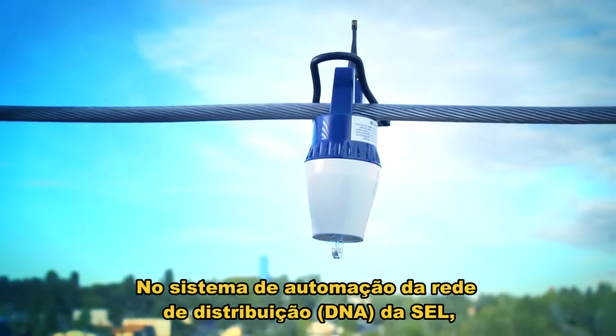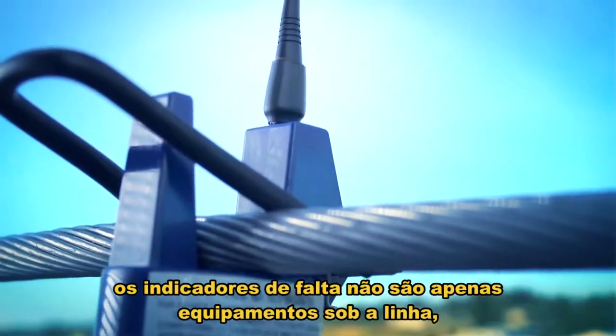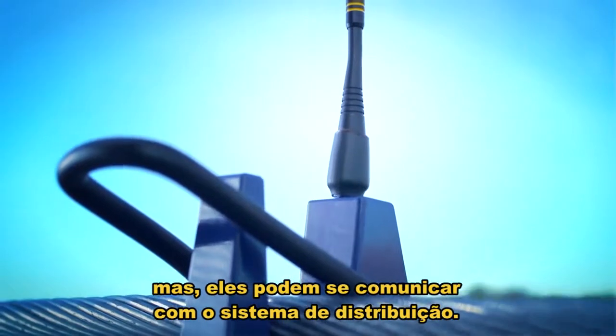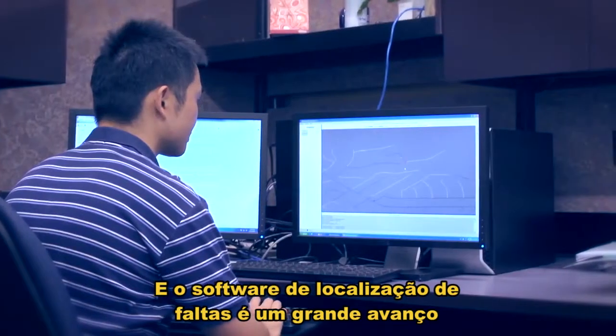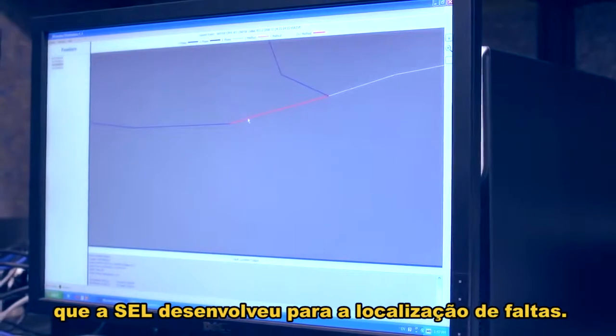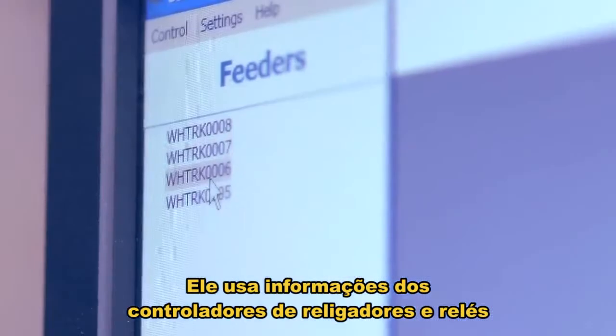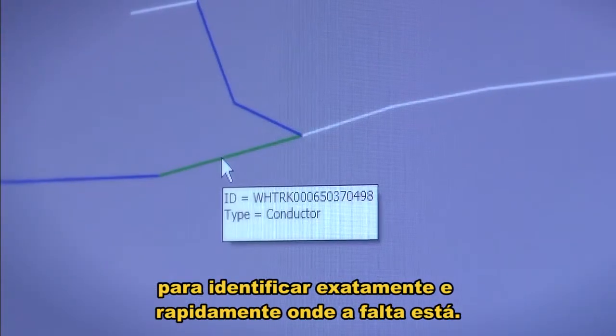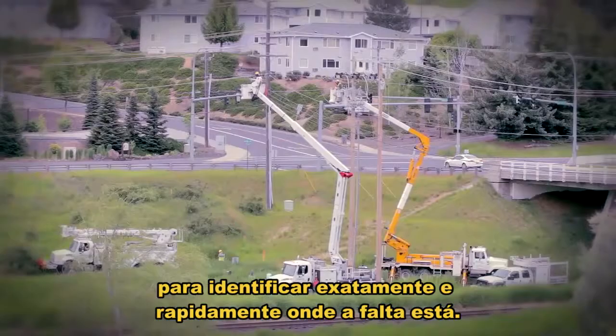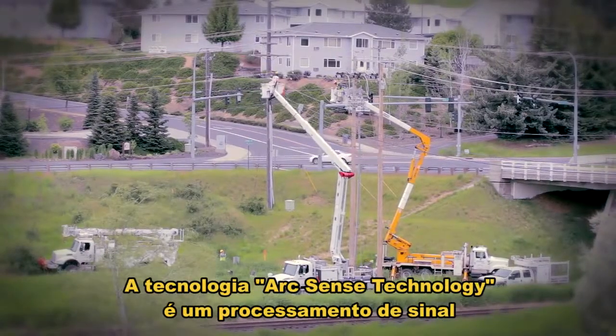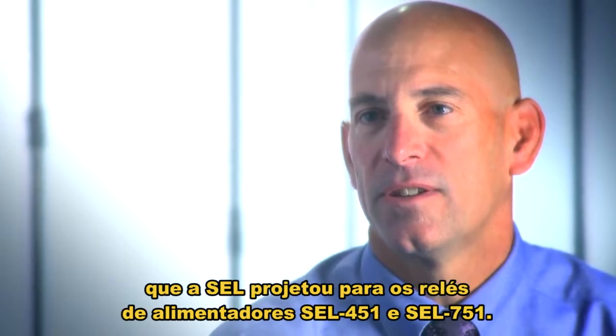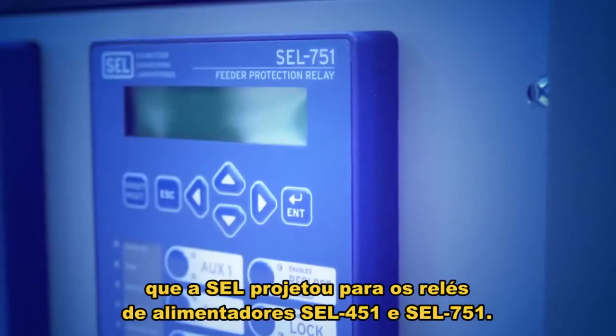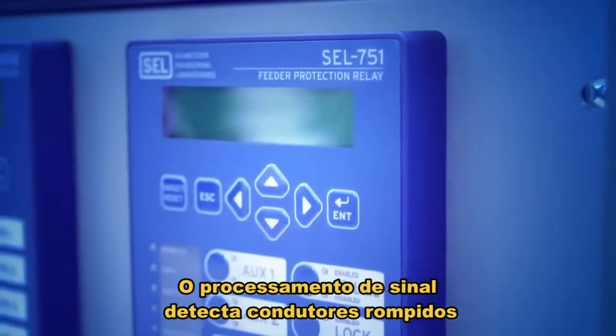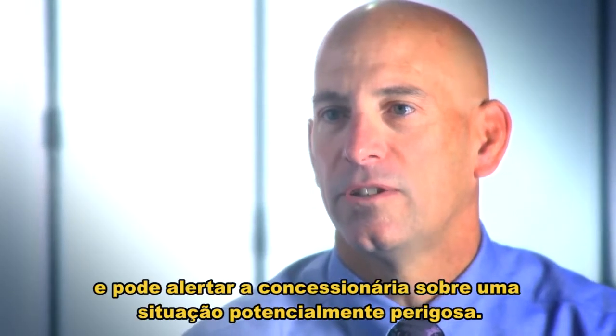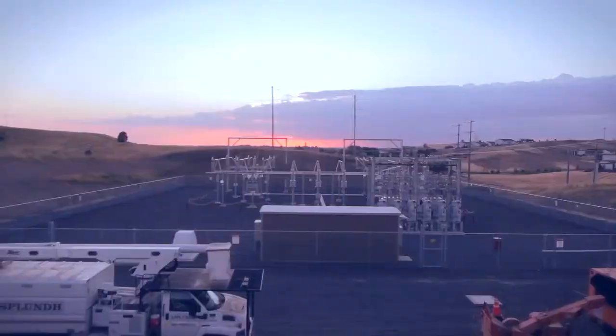With the SEL DNA system, fault indicators are not just discrete devices on the line, but they can be communicating back into the distribution system. And fault location software is a great advancement that SEL has developed for fault location, and it uses information from recloser controls and relays to dynamically identify exactly where the fault is and then automatically send that out so that it can be addressed very quickly. ArcSense technology is signal processing that SEL has designed into the SEL 451 and 751 feeder relays. The signal processing detects down conductors and can alert the utility of a potentially dangerous situation.